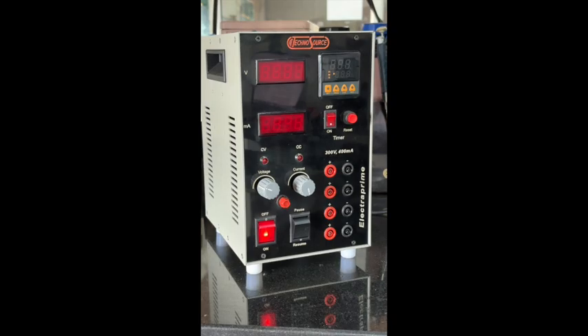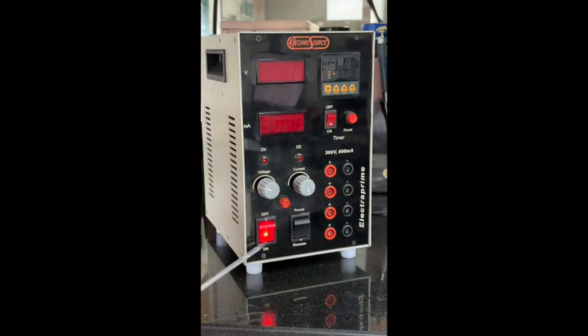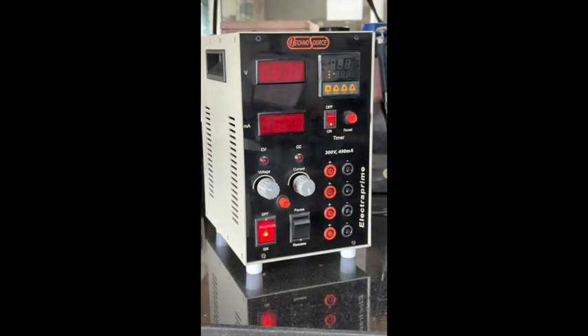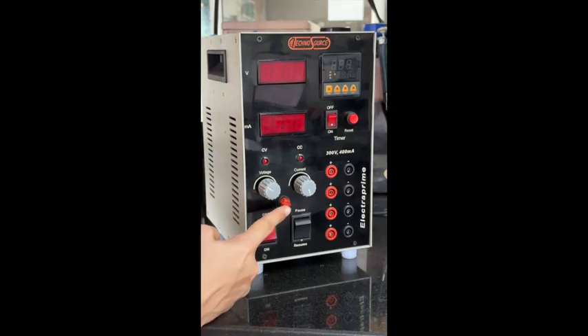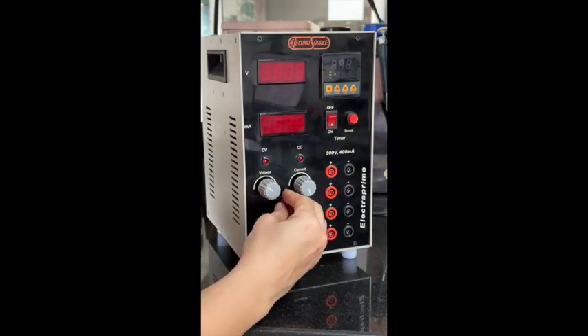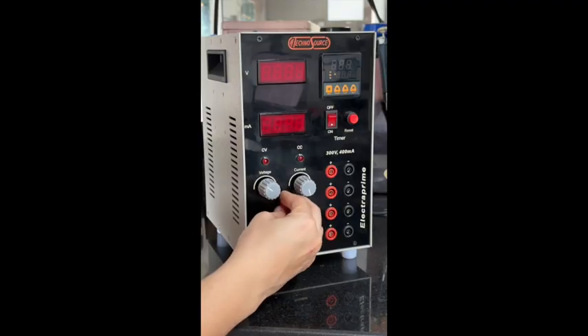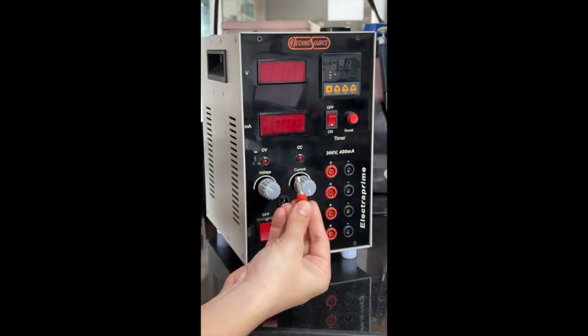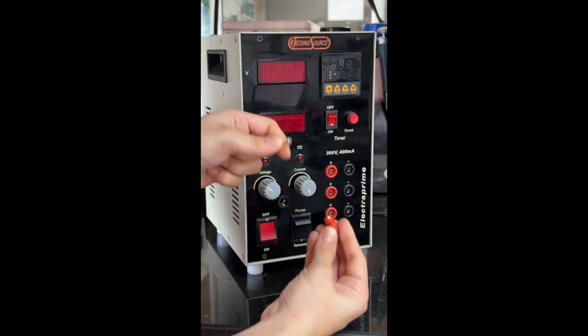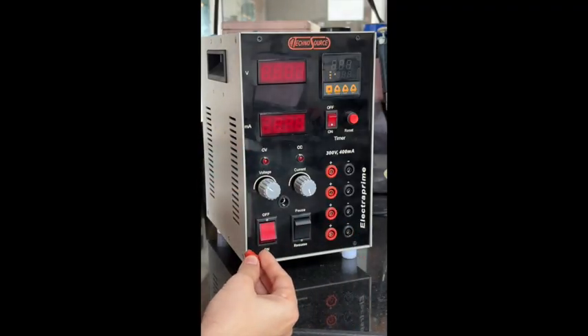Another reason for the power supply to not switch on is when the fuse is blown. In this condition, the illuminated main switch will be lit but no other indicator will be on. To solve this issue, switch off the power supply, open the fuse holder as shown and check the fuse. The wire on the fuse should be intact. If not, replace it with an appropriate fuse.